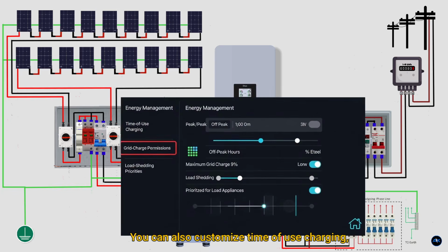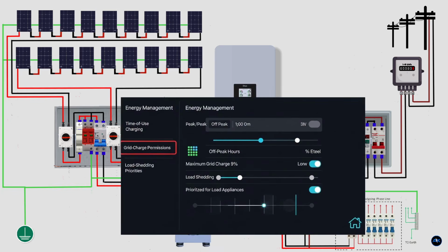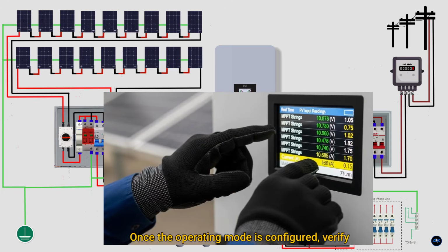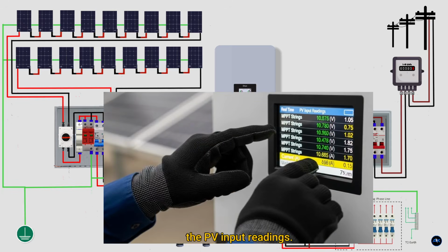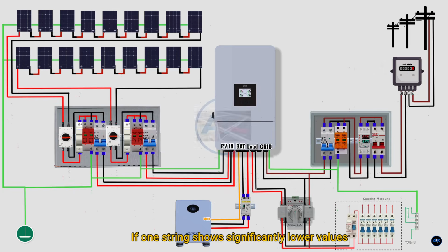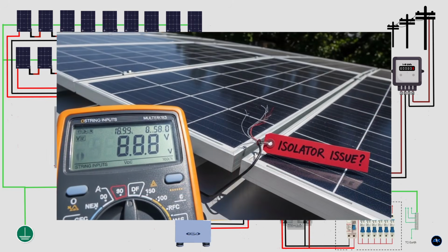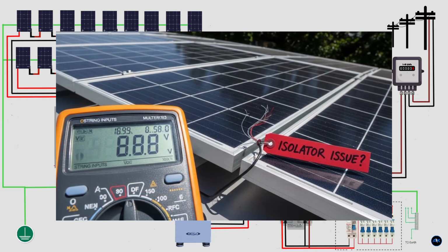You can also customize time of use charging, grid charge permissions, and load shedding priorities depending on your utility rates and backup needs. Once the operating mode is configured, verify the PV input readings. Check each MPPT string for proper voltage and current levels. If one string shows significantly lower values, inspect the panels for shading, loose connections, or isolator issues.